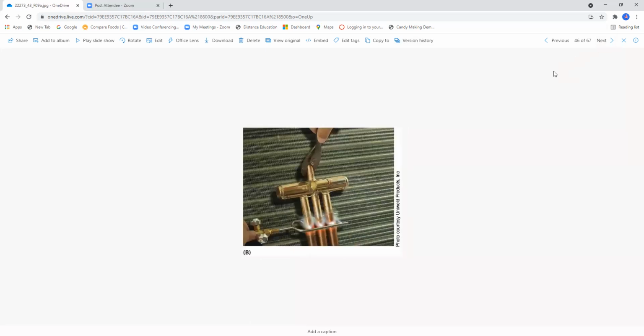Okay, here's the reversing valve. Notice that he's using the tuning fork concept. So in theory, if he does this correctly, he's going to heat this up. Now, the one thing I see wrong with this picture, it's pretty obvious. Do you see any form of heat protection taking place up here? I certainly don't. I think they're just demonstrating the uses. The other thing which this slide does not indicate: you need to run nitrogen through this thing at around 5 psi. We do not want oxygen oxidizing inside of this reversing valve, especially with 410A and POE oil circulating in this system. The POE, in conjunction with the 410A refrigerant, will cause that oxidation to break loose, and you could actually mess up the interior surfaces of this reversing valve.